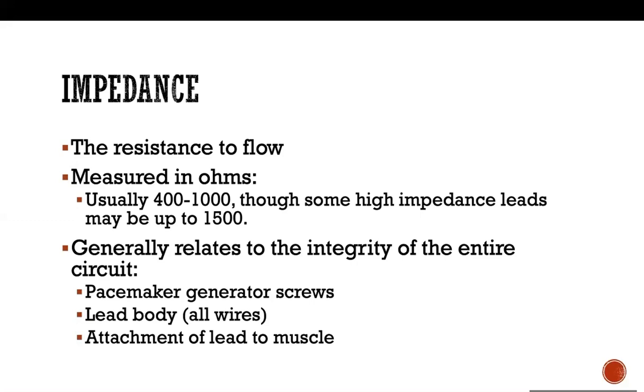So it kind of gives you an idea about the wire itself and the attachment at each end. One is to the device and the other one to the muscle. So if there is a problem with the impedance, it either tells you something is wrong with the wire or something is wrong with the connection to the muscle or the device. So what if we have a very low impedance? That means there is minimal resistance. So what could be the problem?